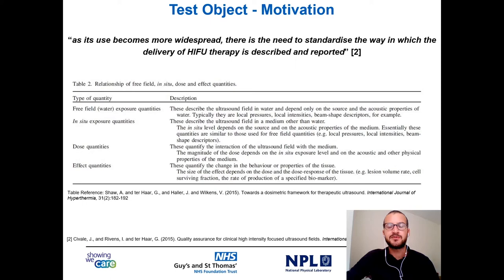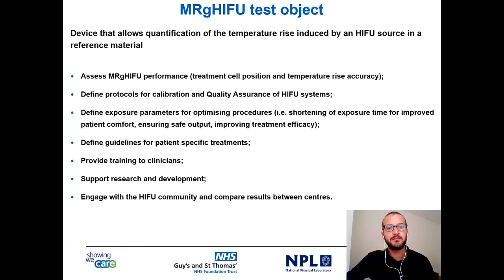For thermal ablation therapy, we need a simple device that allows the quantification of temperature rise induced by an HIFU system in a reference material. This can be useful for many applications, such as the assessment of performance of existing devices, definition of QA and calibration protocols, optimization of procedures, and comparison of results across centers.